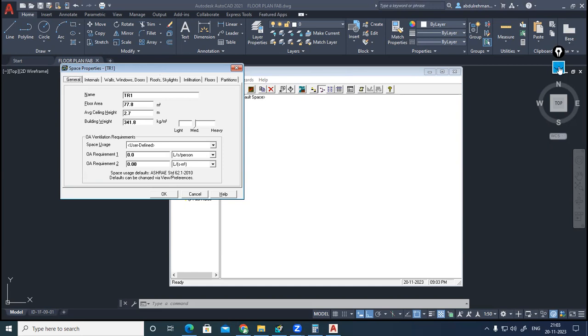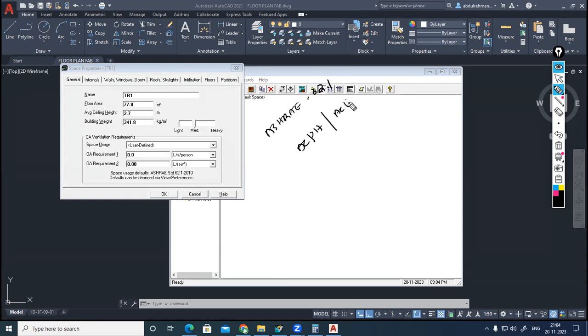Okay. See, for ventilation calculation, different methodologies we have. As per ASHRAE 62.1, for normally comfort air conditioning systems, we can use the ASHRAE 62.1 standard. From that standard, we can take data and give the input. Or some health standards, they'll be recommending, ASHRAE 170, not 90.1. For healthcare facilities, they'll be recommending fresh air changes per hour, ACPH or ACH, air changes per hour four, or sometimes means fresh air, not the entire recirculation. Air changes per hour four, they will be recommending. Anyhow, one by one, we can discuss.